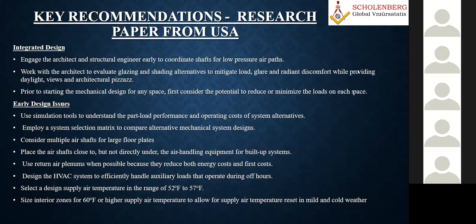When I take this one, how I have to interact with my fellow services, other electrical engineers, architects, and structural engineers - as much as possible you keep the air shaft very close to the air handling unit, so you can avoid pressure drops from duct routing, and use the plenum, because if you use the plenum, it will help reduce energy cost. But maybe because of space constraint you may not be able to use that, and that will also have an effect on the performance of your air handling units.